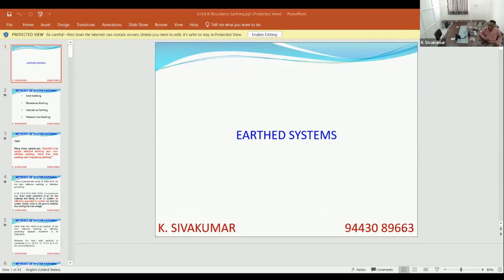But there is a danger. Since the fault current is returning through the PE conductor or the earth conductor, there will be a potential rise, a voltage drop proportional to the product of fault current and resistance. There will be a potential voltage appearing at the generator neutral terminal also, because the neutral is not isolated. The other thing is also true. If the generator is feeding and the neutrals are linked, the transformer which is switched off will have a potential at its neutral.